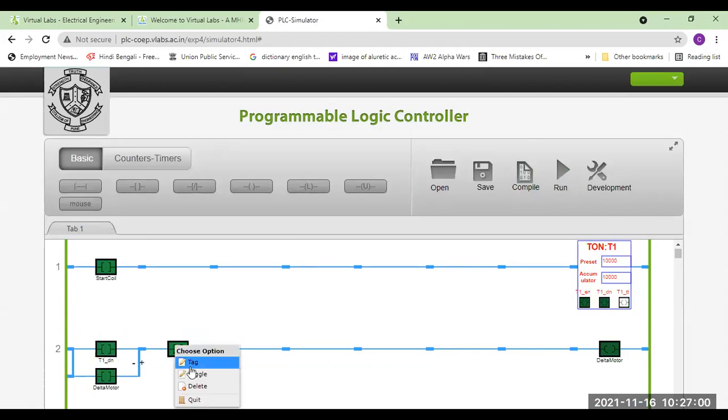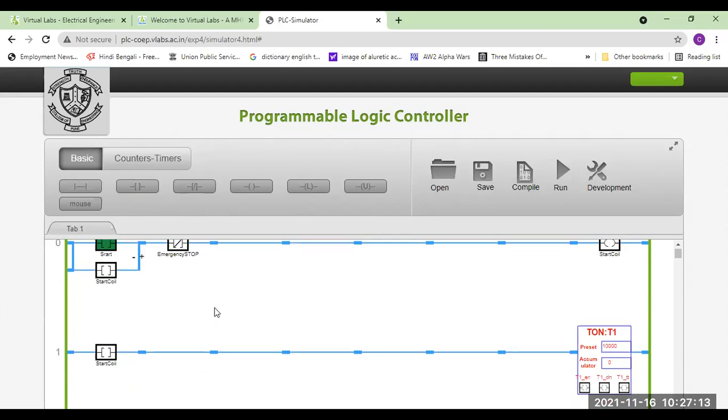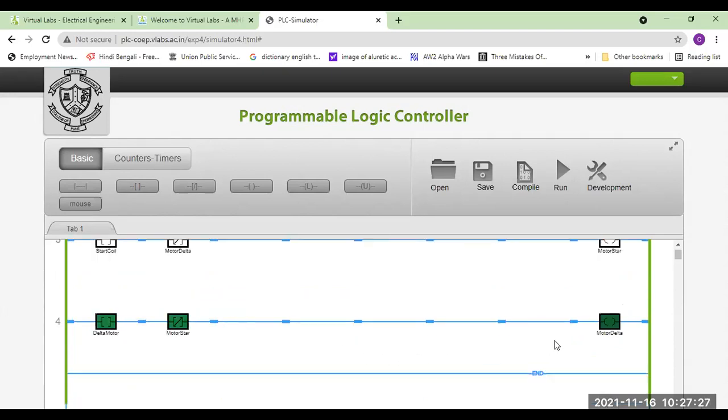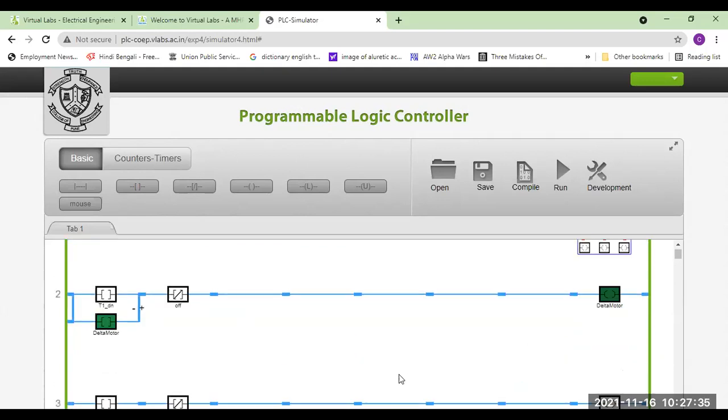Delta, now we have to turn it off. No, it is not turning off. Look, once you latch it, it remains latched, so that it should turn off. Delta motor is another here. Yes, delta motor is here. That's why it is not going to the off stage.